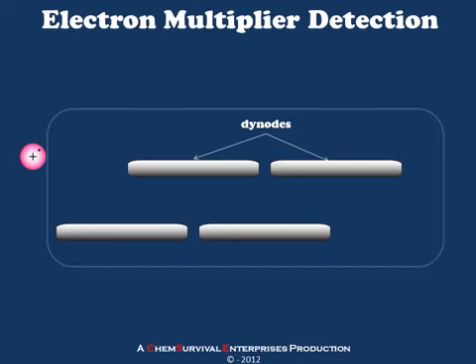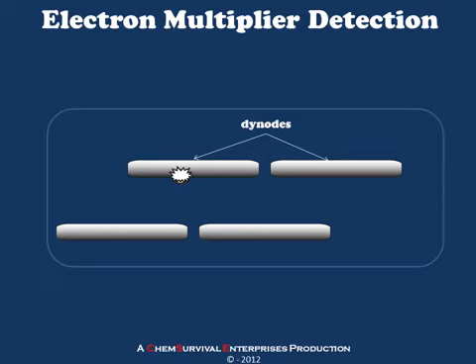One method of detection frequently used in mass spectrometry is the electron multiplier. An electron multiplier is a series of special plates known as dynodes, represented here by these gray-colored bars. Dynodes are made of a material which ejects electrons in response to physical impacts, such as the impact of a cation or the impact of an electron. This means that if our analyte ion strikes a dynode, it's expected to perturb the dynode in a way that causes the release of at least one electron, sometimes more.